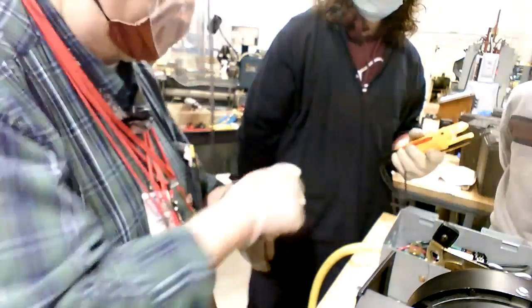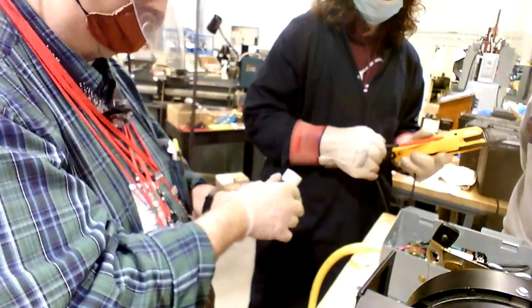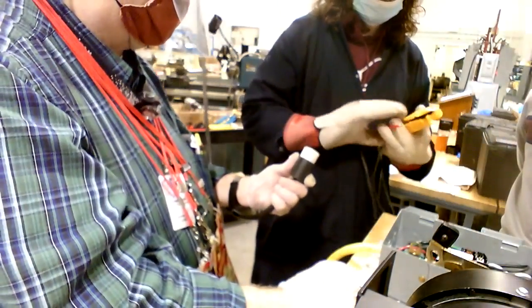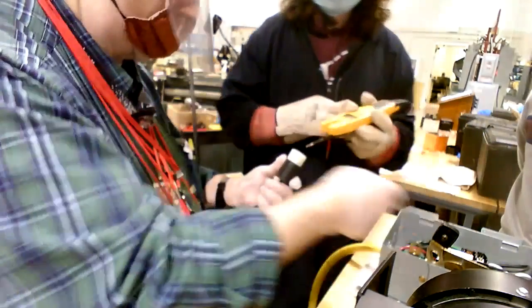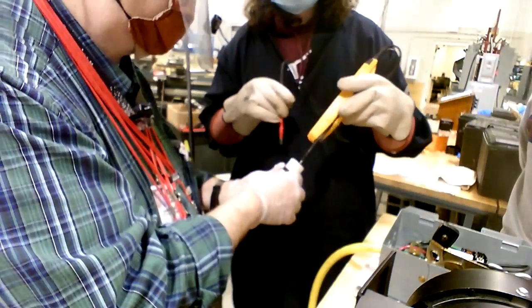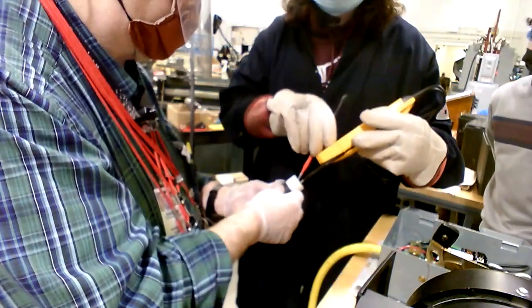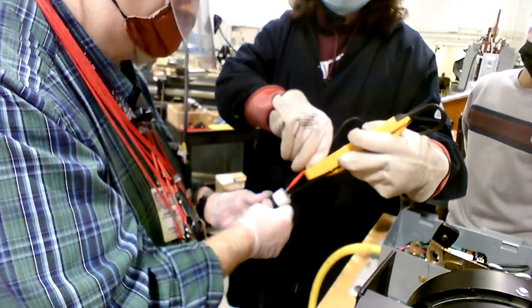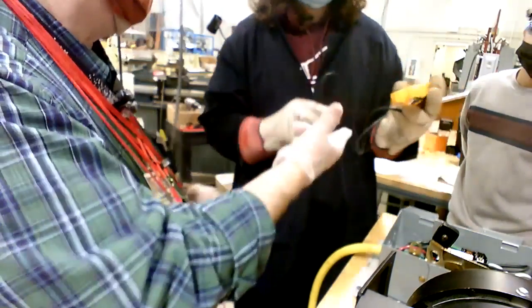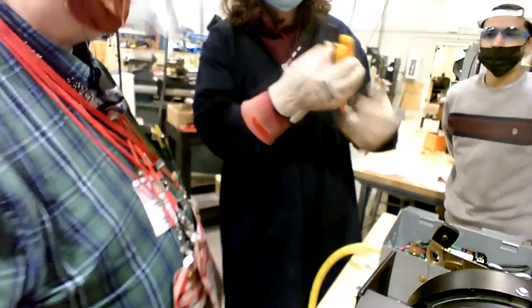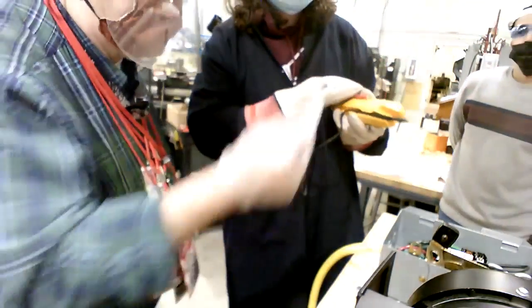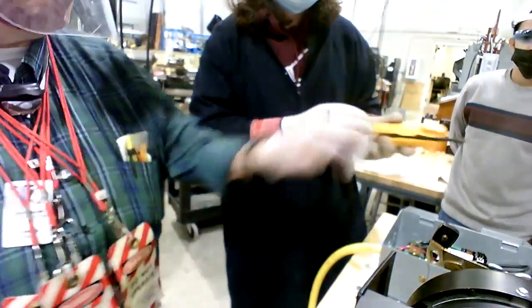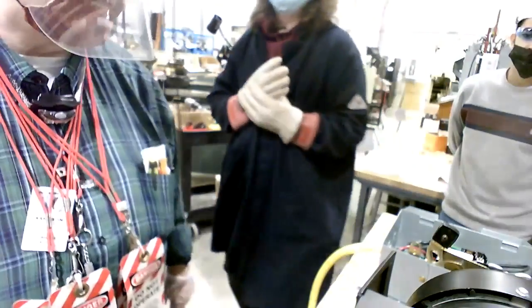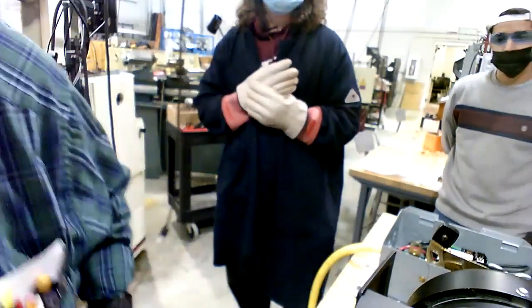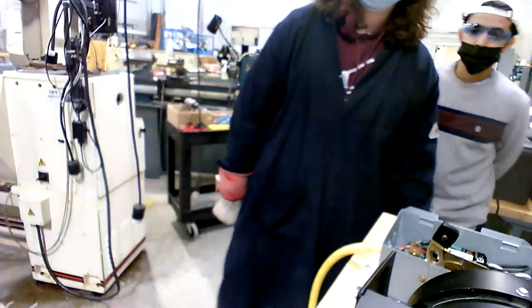To check the meter, stick it in that hot and that neutral right there and make sure the meter's working before you go test any circuit. Got 121. So you know the meter's good. The meter's not bad. So that's the OSHA recommendation: check on a known power source, and then check what's going to be dead. Then you know that meter's okay. So it's dead, it's locked out, and that will let you do the reversal now.